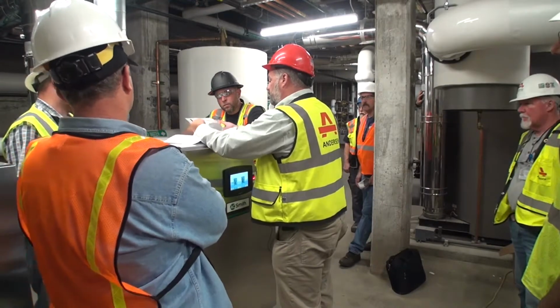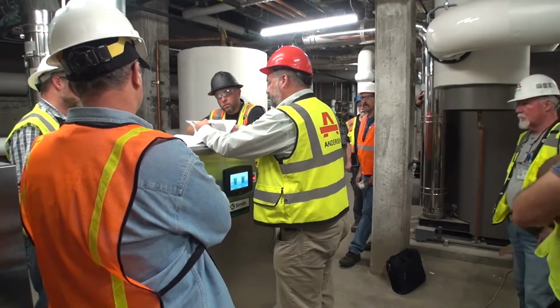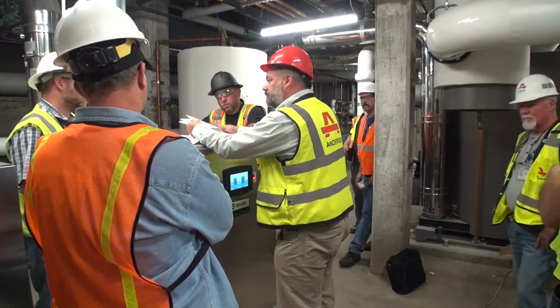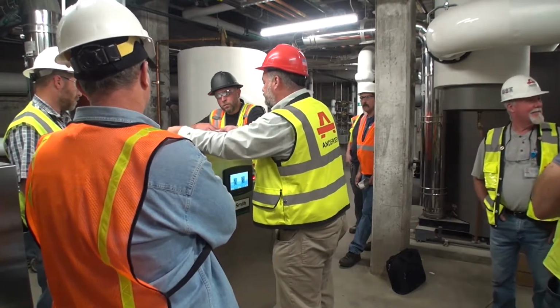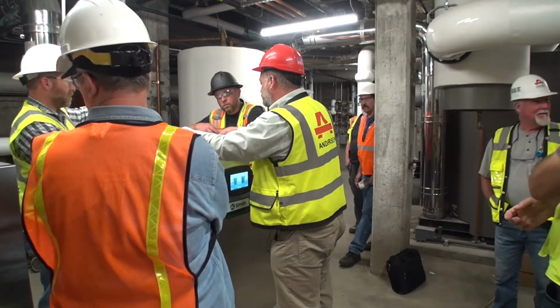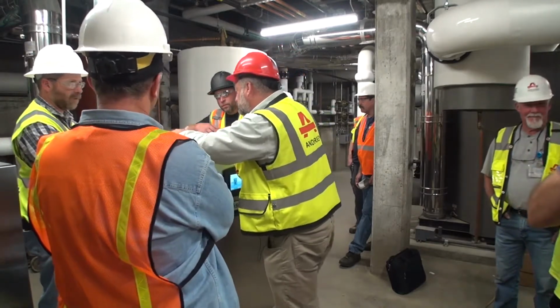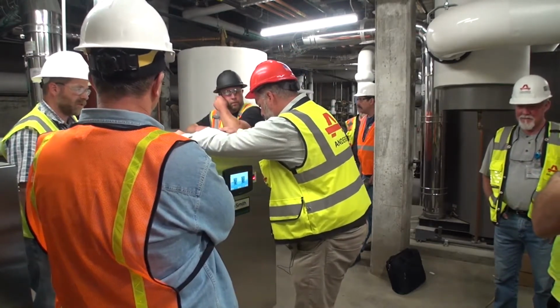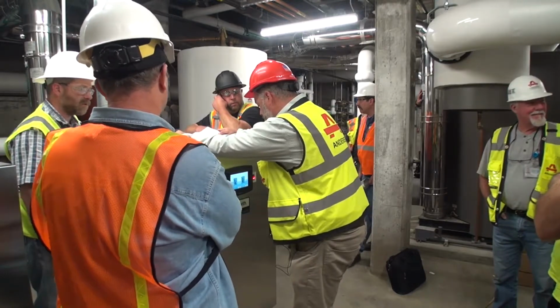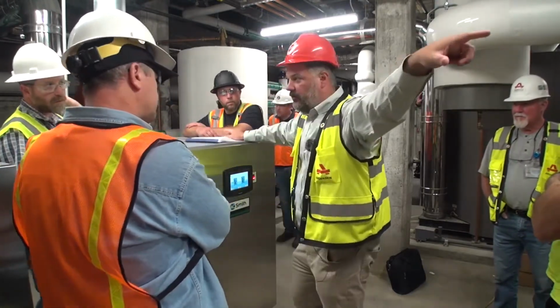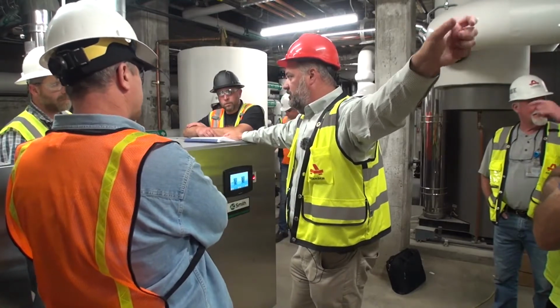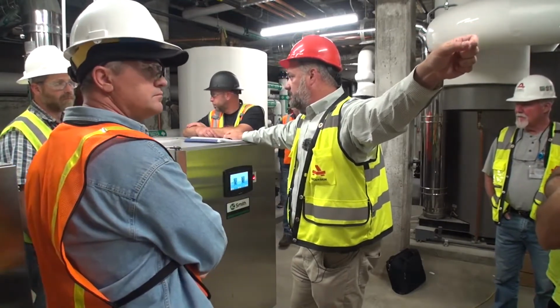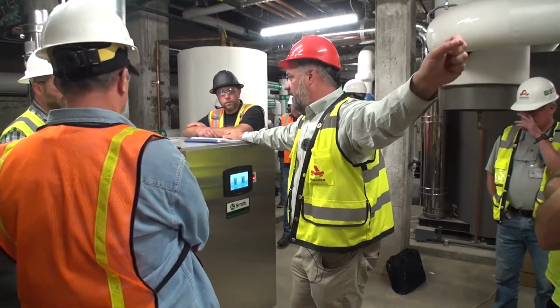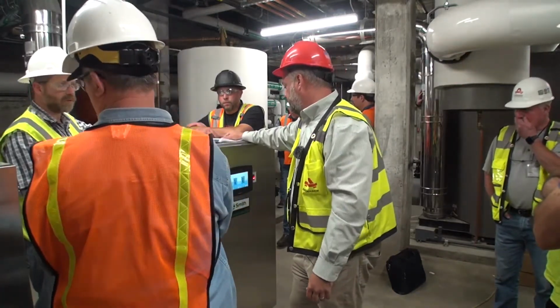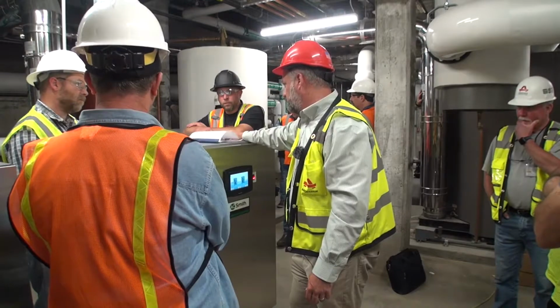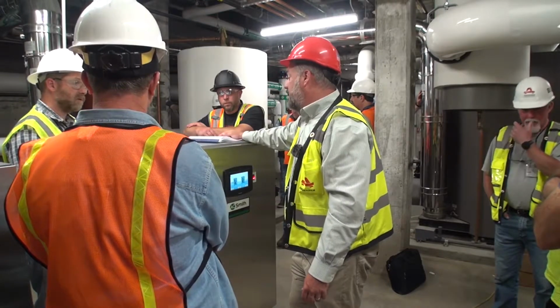Is this hot surface ignition or is it electronic ignition? Electronic. Yeah. Do they have a photo eye to confirm that it's lit, or does it just go on a thermal sensor that the pilot was established for? It's going to show over here, there's a little burner icon that turns on when this thing's engaged, so it'll show on 1, on 2 on the icon. And that's just so we know for troubleshooting if you can't get it started, whether it's tested or not. Yeah, I mean, there's going to be an error.